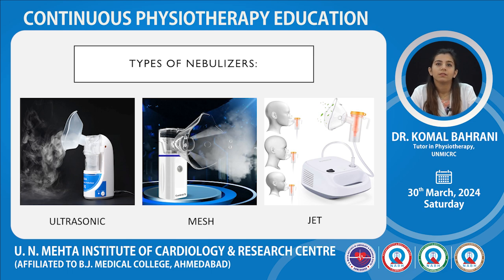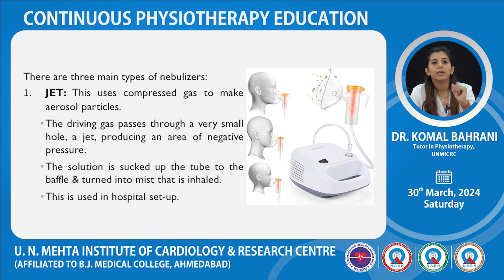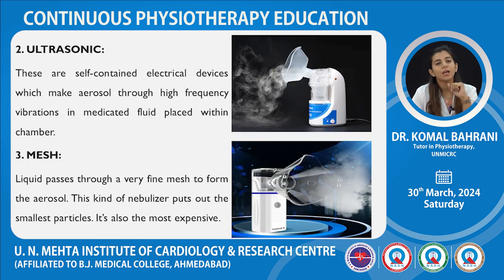Now, types of nebulizers. There are three kinds of nebulizers we use: ultrasonic, mesh and jet. We'll firstly discuss jet nebulizers because they are commonly used in hospital setups. First, jet. This uses compressed gas to make small aerosol particles. The driving gas passes through a very small hole, a jet, producing an area of negative pressure. The solution is sucked up the tube to the baffle and turned into mist that is inhaled, and this is used in hospital setup. Second is ultrasonic.